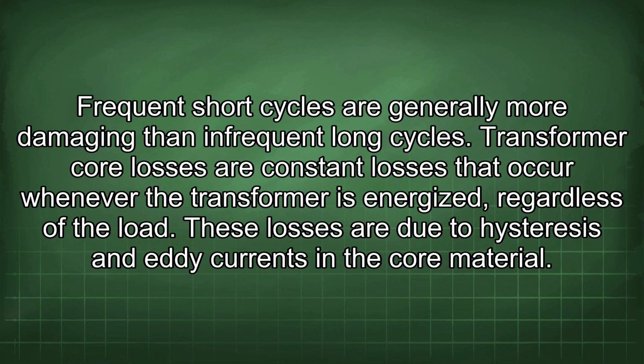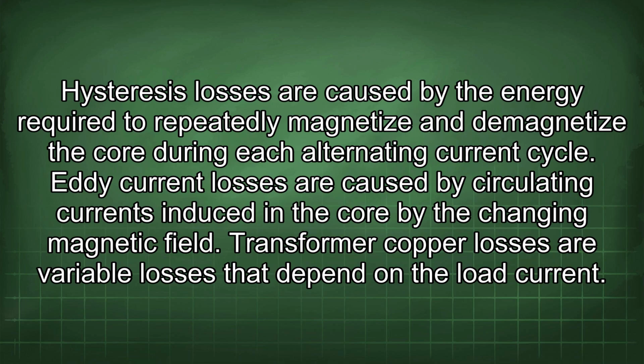Transformer core losses are constant losses that occur whenever the transformer is energized, regardless of the load. These losses are due to hysteresis and eddy currents in the core material. Hysteresis losses are caused by the energy required to repeatedly magnetize and demagnetize the core during each alternating current cycle. Eddy current losses are caused by circulating currents induced in the core by the changing magnetic field.